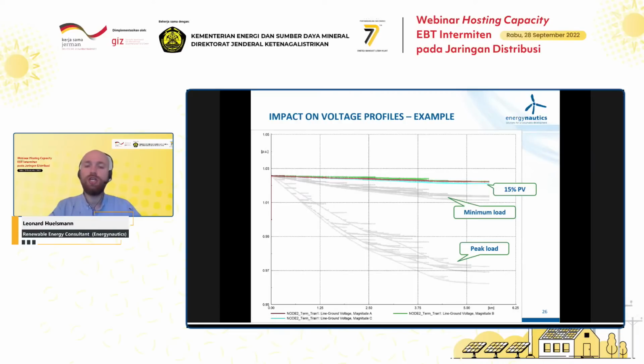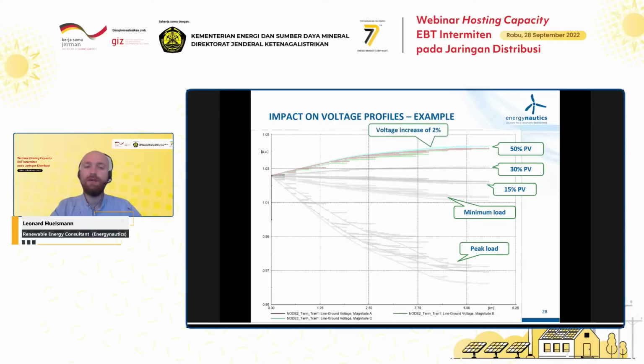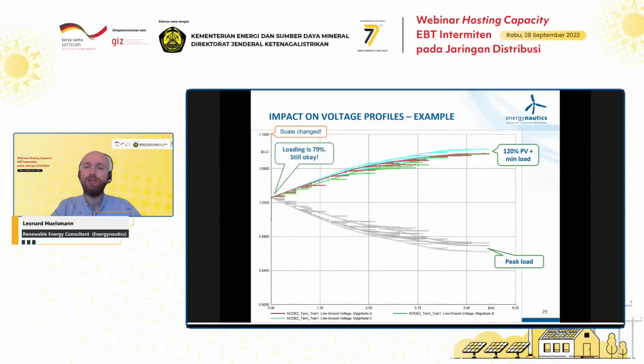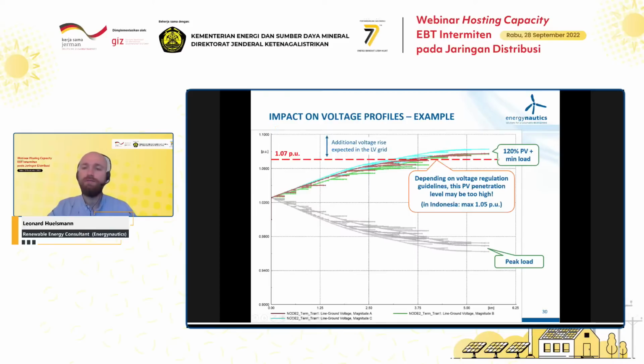And what we see is that initially it actually has an improving impact, because we want to have a flat voltage profile in our network. But as more and more PV generation is added, the voltage rise will be higher and higher. And at some point, we may have added a lot of PV generation in our distribution feeder, however, above a limit that is not allowed anymore. And so in Indonesia, for example, the maximum voltage level regulated by the grid code is 1.05 per unit. And a certain PV penetration might then be too much, which would not be allowed anymore.